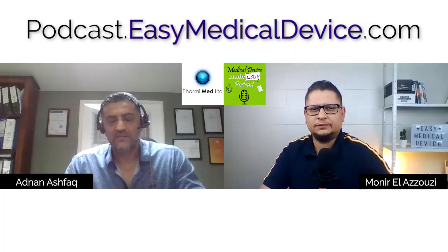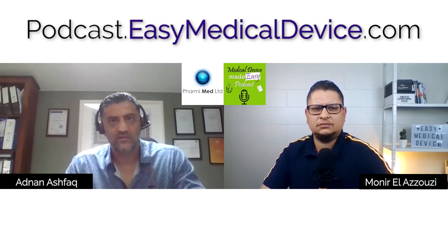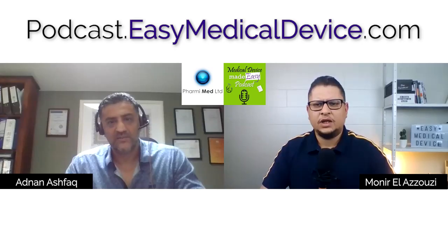Okay. There are other applications also. So there is 12207, 61508, and 90003, which is also for software development lifecycle, but they're not specifically for medical devices. 62304 is specific for medical devices.